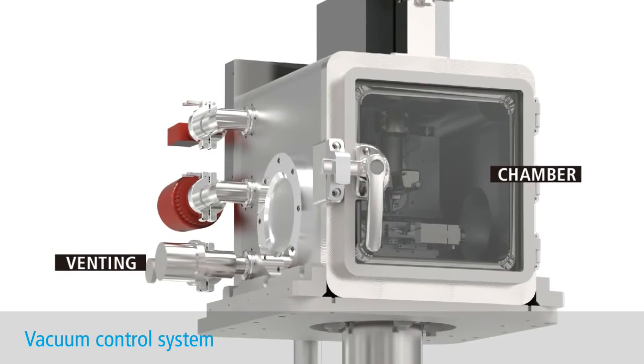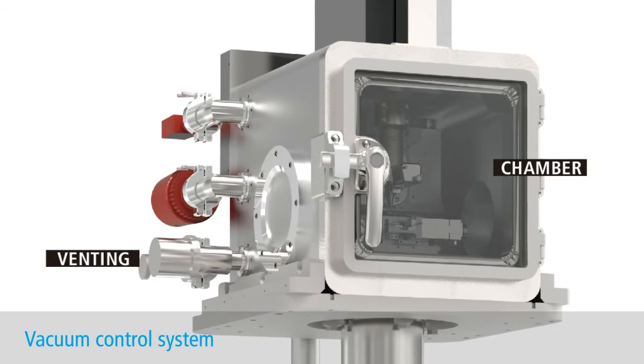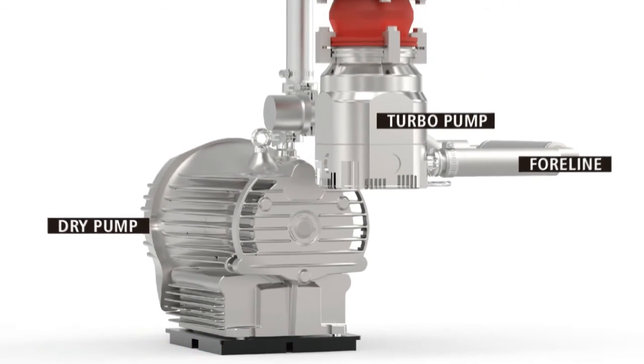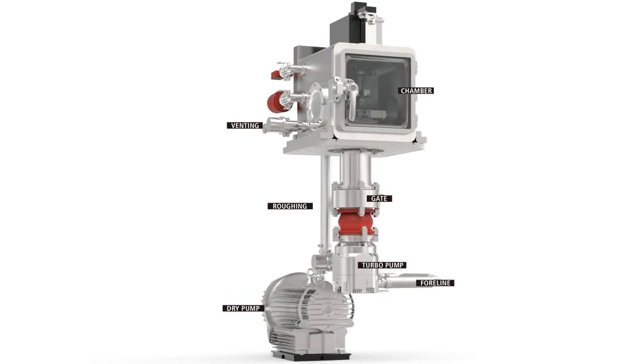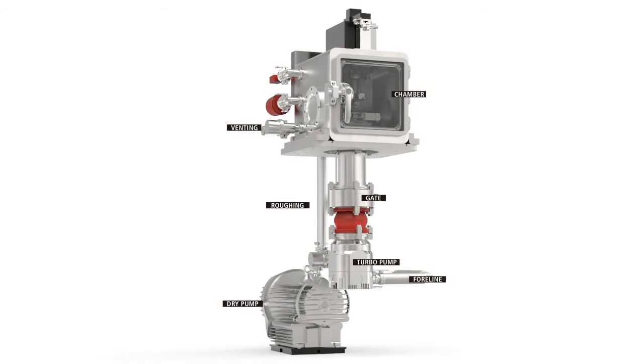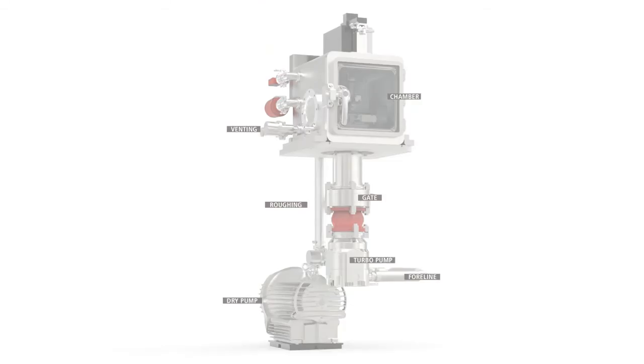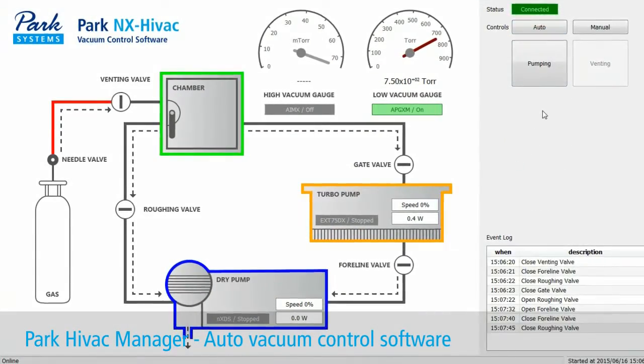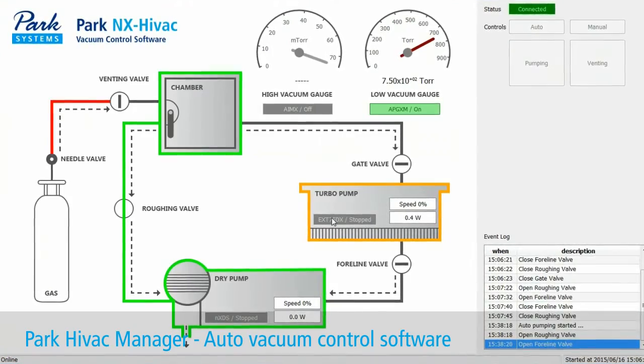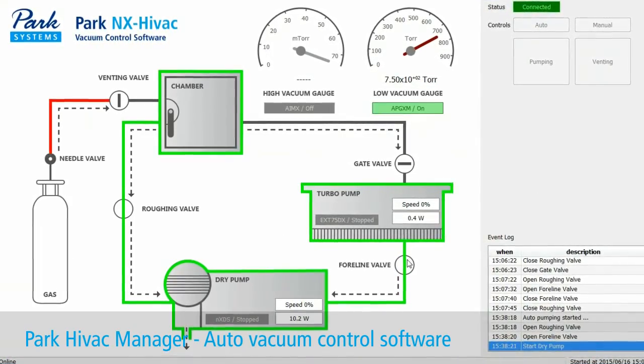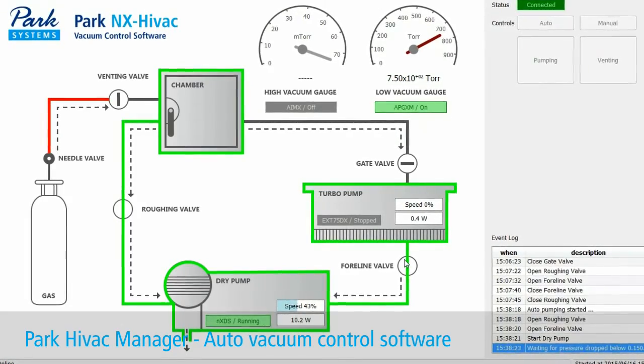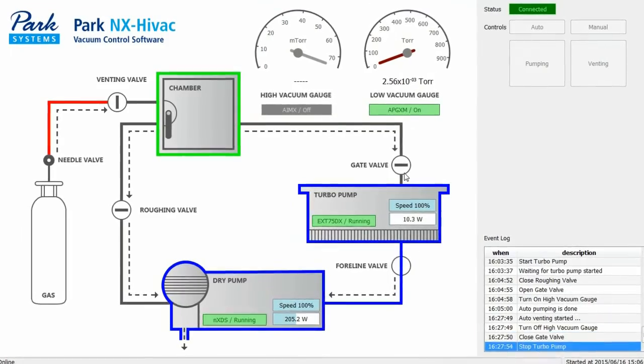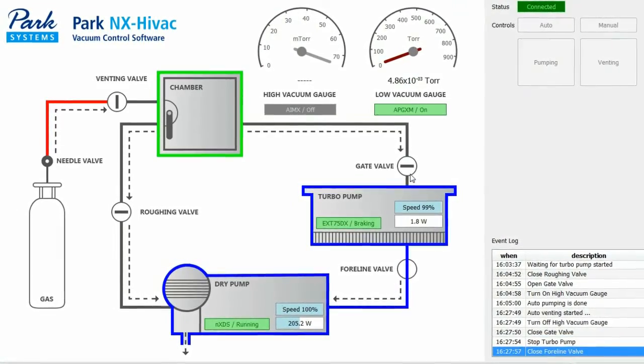Moving on, we have the vacuum control system. The HiVacuum is controlled by turbo and dry pumps installed here under the system panel. One noteworthy advantage of this design is that the pumping will not affect system noise levels during sample imaging. And here is another significant development: our Park NX-Hivac Manager software. This program enables single-click, automatic high vacuum control that uses intuitive color schemes and other interface elements to instantly alert the user visually what phase of vacuum preparation the system is currently in.